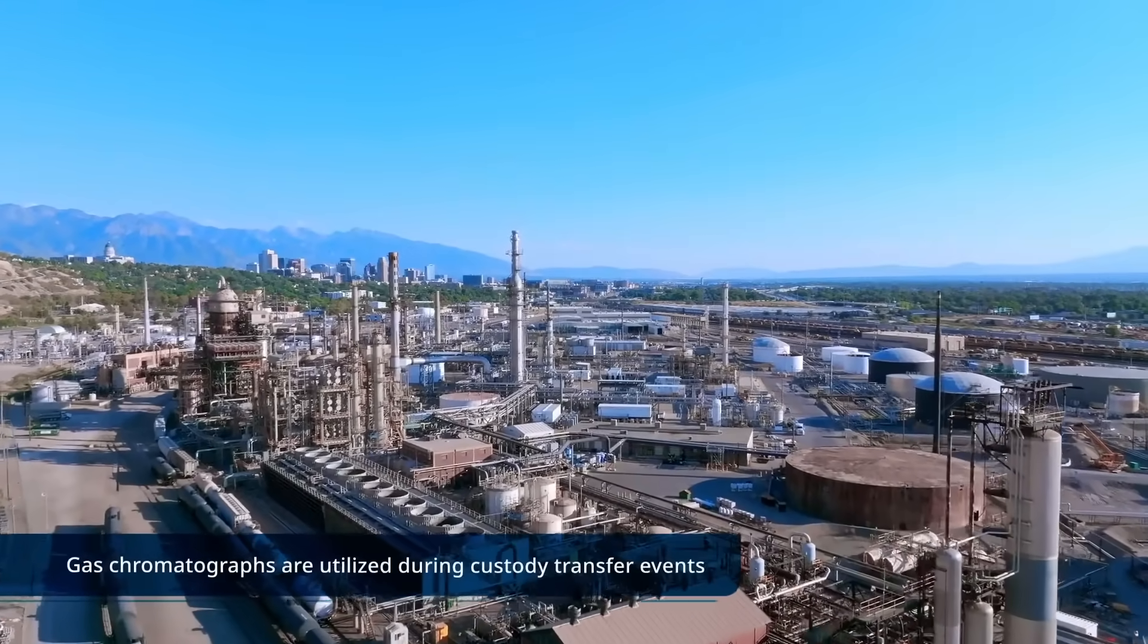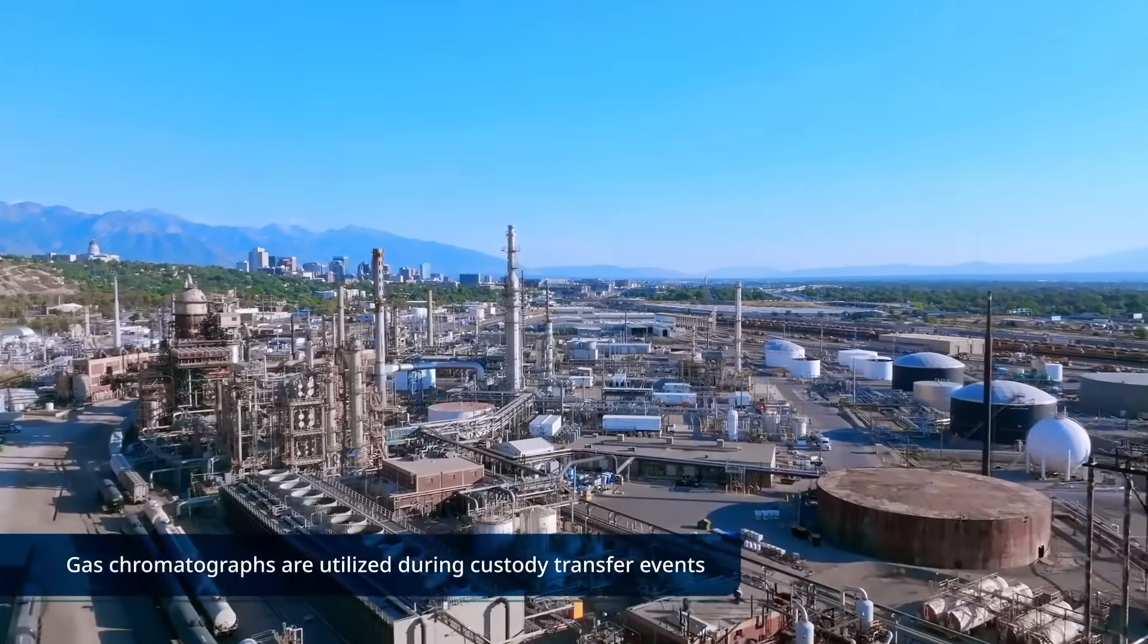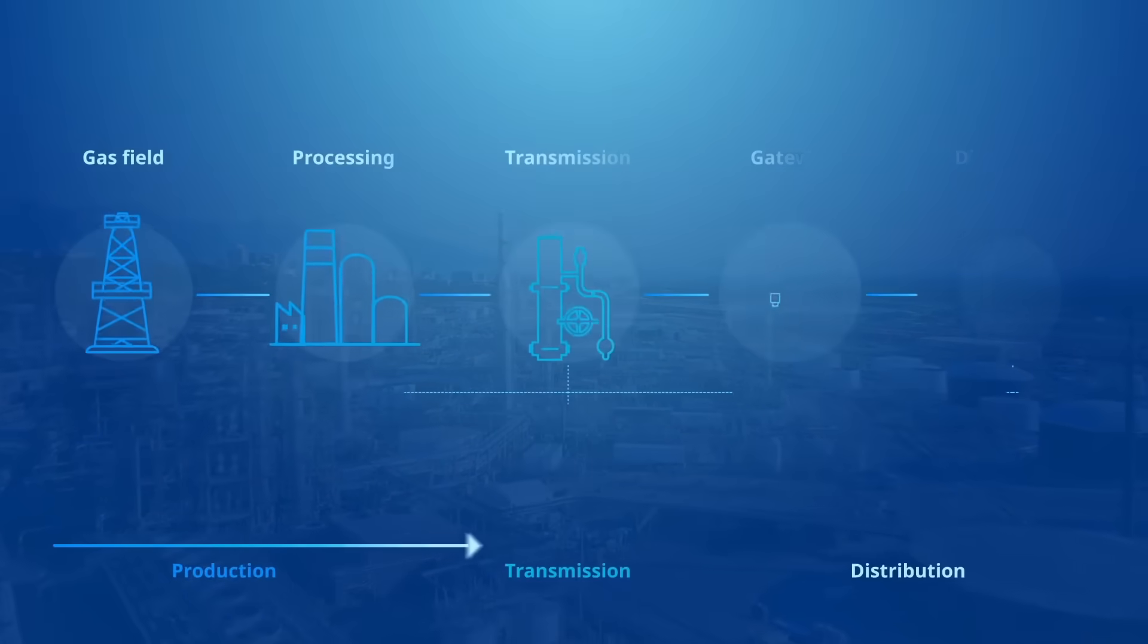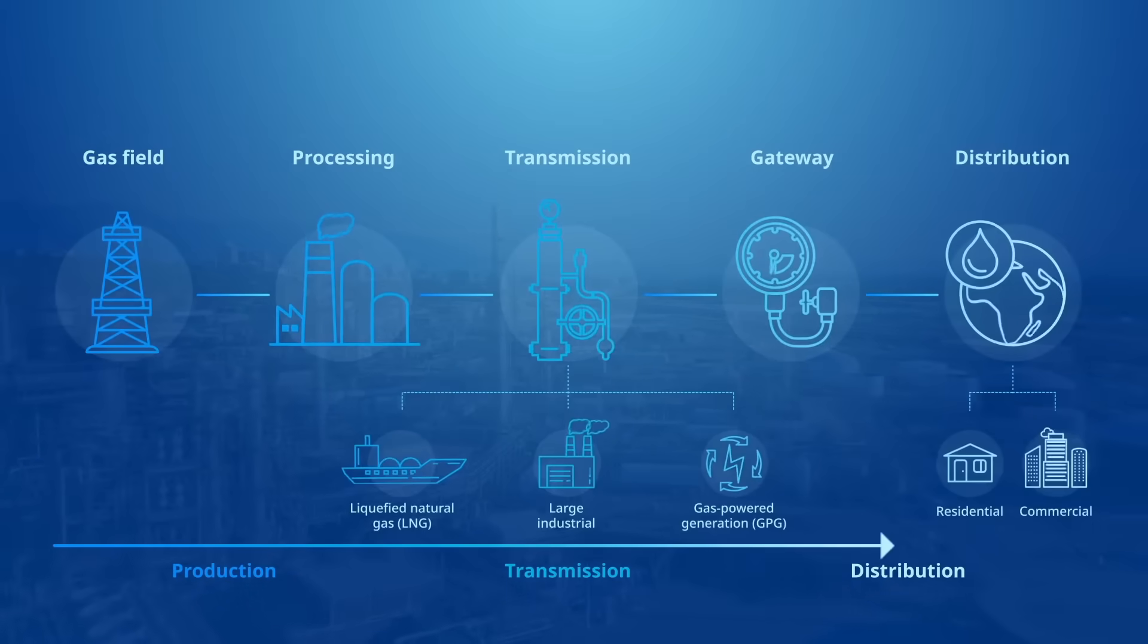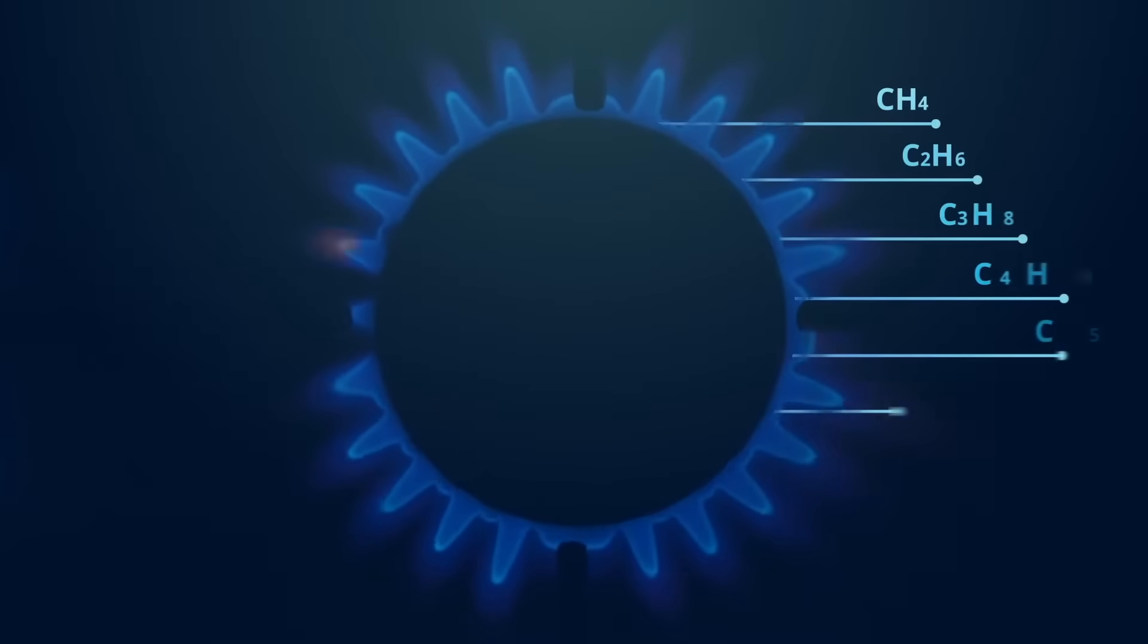Throughout the natural gas industry, gas chromatographs are utilized during custody transfer events, when the gas changes ownership between sellers and buyers, to measure the component content of the gas and calculate its energy value, usually expressed in BTU or calories, as well as the Wobbe index of the gas.